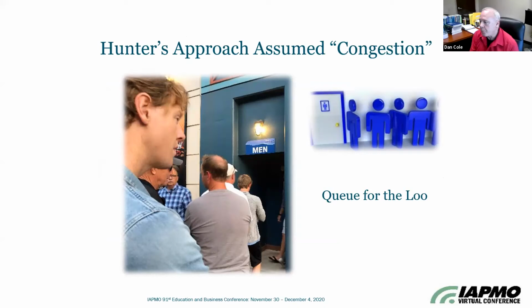Congestion is basically a condition of peak demand where there would be a repeated use of fixtures during peak hour. And the result would be a high probability of fixture use during that peak hour. But such frequency is not found in a single family home. So new p-values, the frequency of fixture use, would have to be determined for residential dwellings.